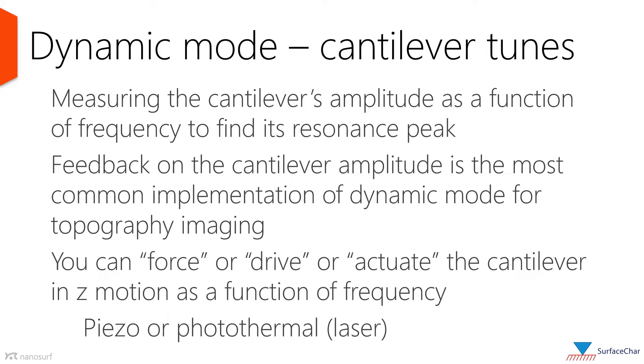Dynamic mode is a little more complex. In order to use a cantilever in dynamic mode, it first needs to be tuned. Tuning the cantilever means finding its resonance frequency and oscillating it at or near it, using oscillation amplitude as a feedback loop set point. The two methods to oscillate the cantilever are piezo, which is the traditional method, and photothermal, which will be discussed later.